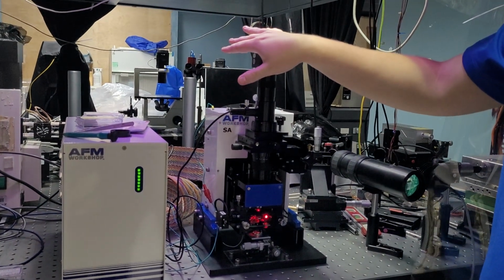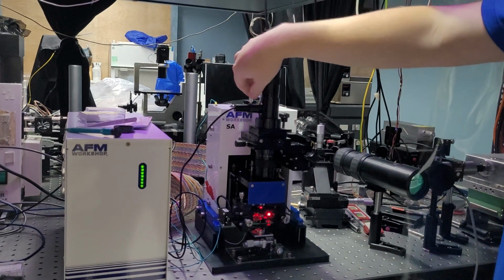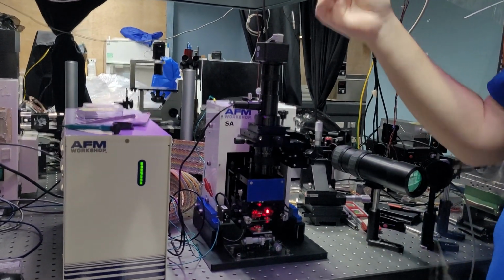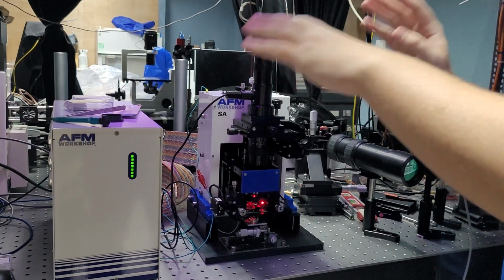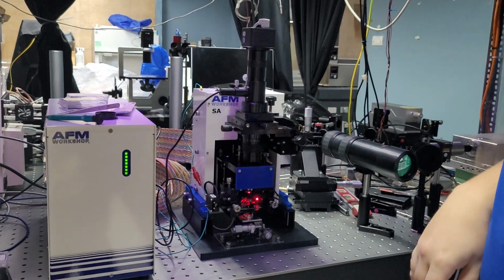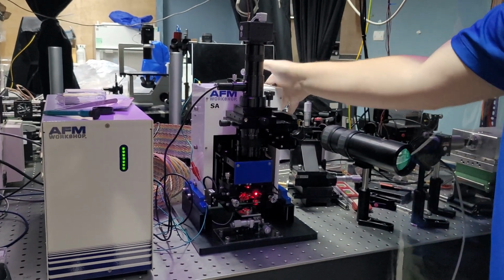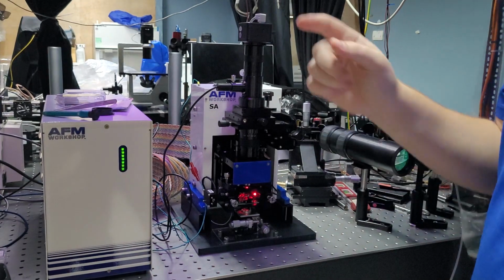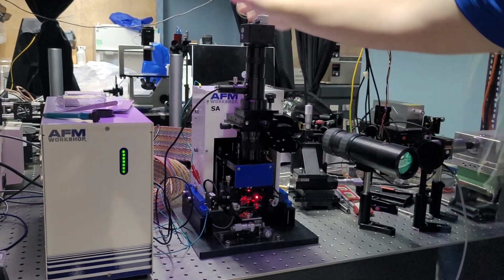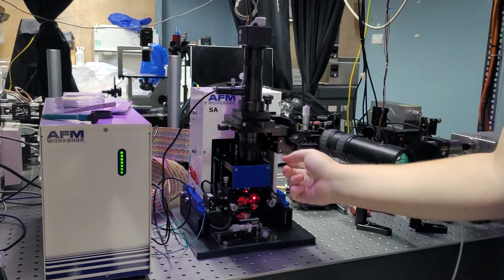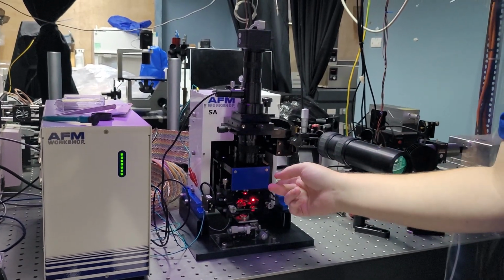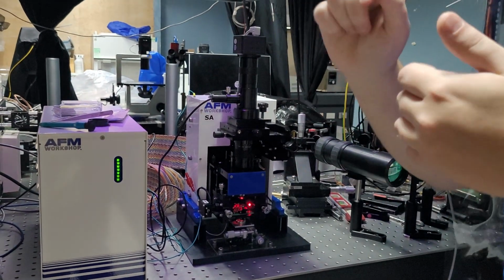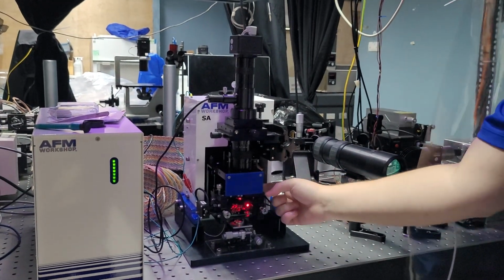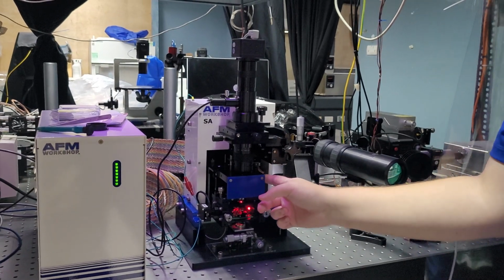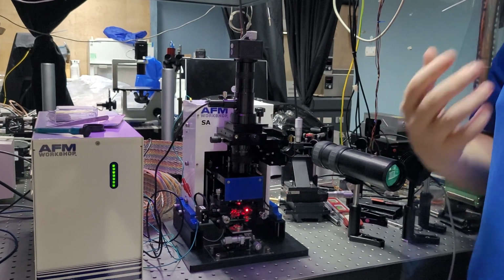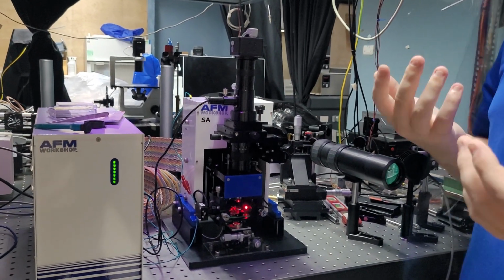These should not need to be changed, but obviously if you're going to eventually put it up onto an optical table, then everything is going to have to be taken apart. In addition to that, if you ever need to move the AFM, as in pick it up and move it somewhere, everything should be disconnected, so the cables at the back should be disconnected, and those red brackets that I showed you earlier should be put on. You don't have to tighten them all the way, you don't have to torque down on them, just screw them in to the point where it will stabilize this. Because this is very fragile, and if you break it, you have to send the entire thing back to us. And that's not fun.